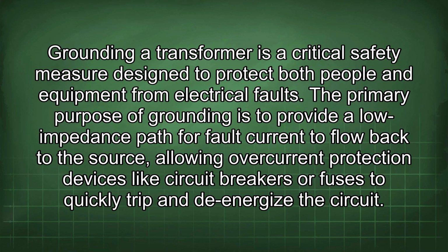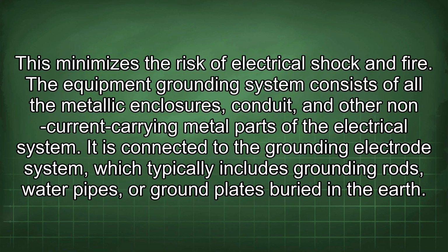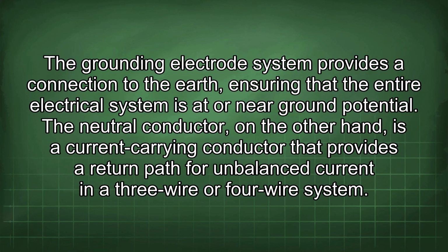Grounding a transformer is a critical safety measure designed to protect both people and equipment from electrical faults. The primary purpose of grounding is to provide a low impedance path for fault current to flow back to the source, allowing overcurrent protection devices like circuit breakers or fuses to quickly trip and de-energize the circuit. This minimizes the risk of electrical shock and fire. The equipment grounding system consists of all the metallic enclosures, conduit, and other non-current carrying metal parts of the electrical system. It is connected to the grounding electrode system, which typically includes grounding rods, water pipes, or ground plates buried in the earth. The grounding electrode system provides a connection to the earth, ensuring that the entire electrical system is at or near ground potential.